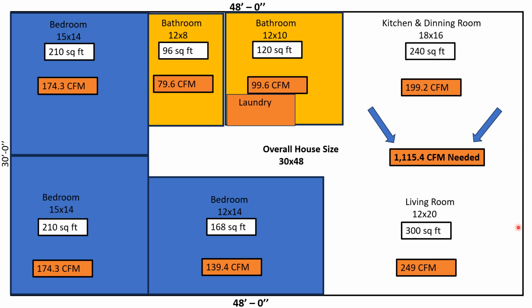This all added up is going to give us 1115.4 CFMs. Like I said, this is strictly for demonstration purposes only. This isn't a real house. This is just to let you understand that if I take this house and take each of my rooms and get the square footage from each room, and then I take my 3 ton, 3 times 400 is 1200, and divide that into the 1440 square feet area, I get 0.83. And so I'm going to go with a 0.83 number to make sure I get the right amount of CFMs from my unit for these areas.